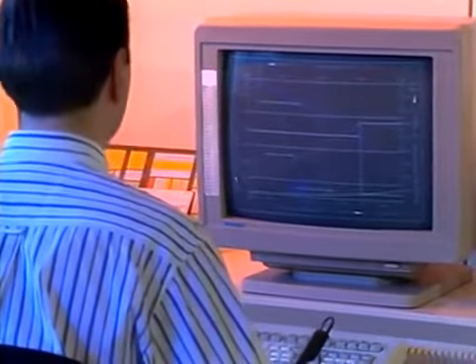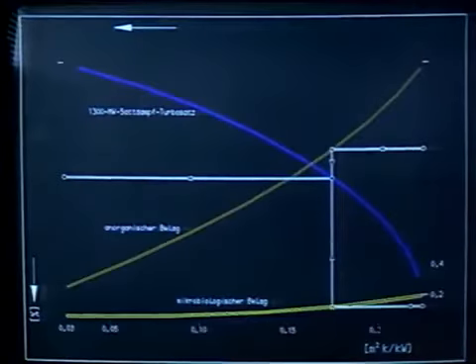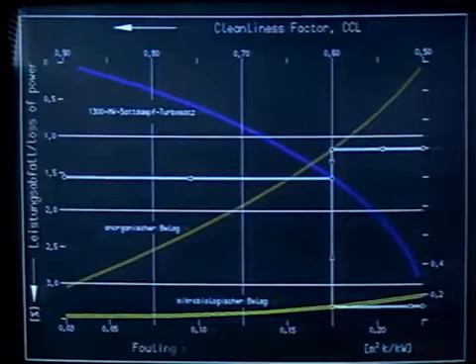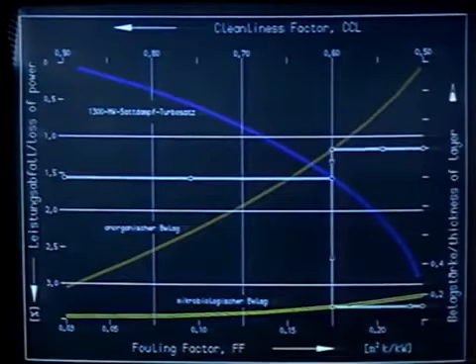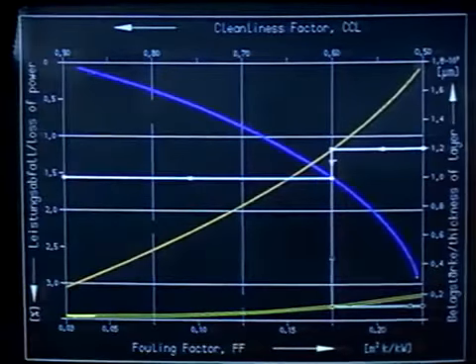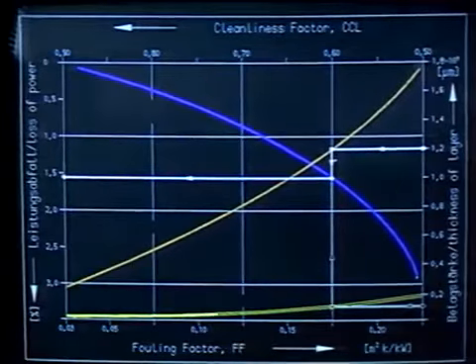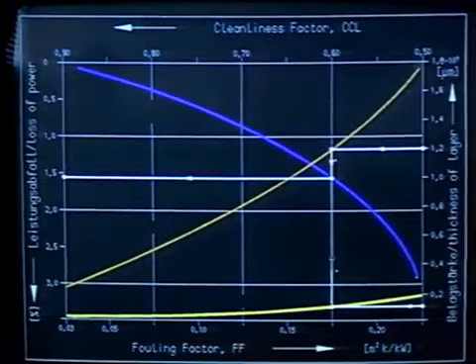All these fouling deposits have operating consequences. In the condenser of a 1300 megawatt power station, a 0.12 millimeter thick layer of calcium carbonate reduces output by 1.6%. Bioslime, only 0.026 millimeter thick, will cause a similar output loss in a titanium tube condenser of a power station cooled with seawater. Though almost invisible to the human eye, these unwanted deposits still trigger substantial power losses.